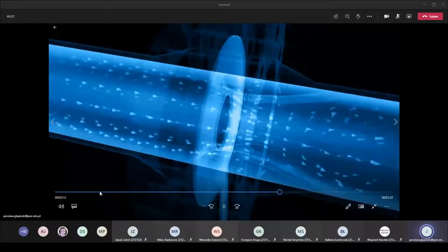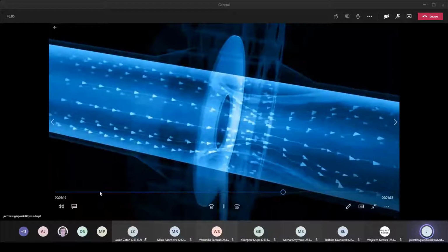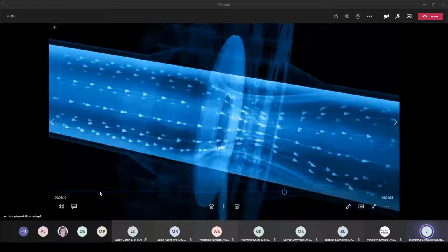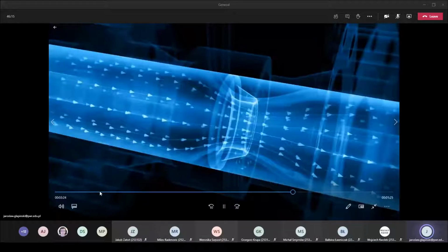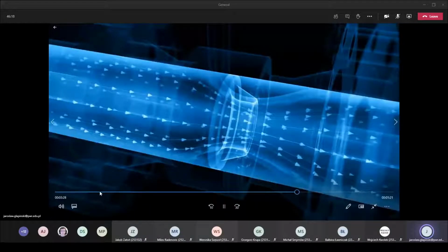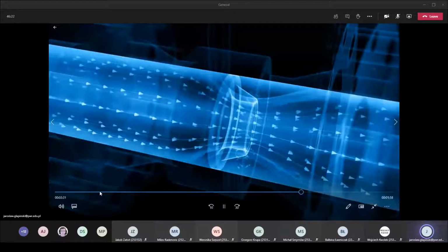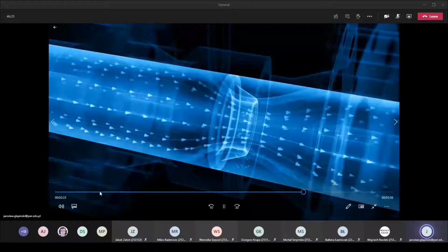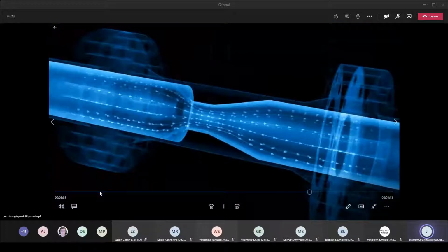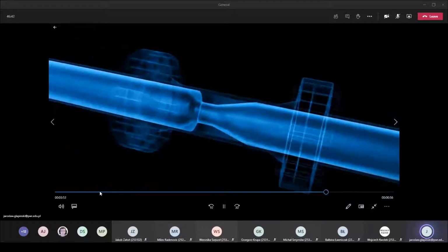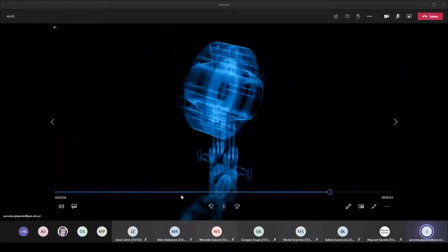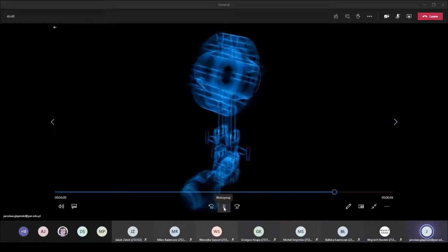This demonstration shows that an abrupt restriction generates severe turbulence in a fluid. Nozzles with a rounded, funnel-like inlet clearly reduce turbulence and thus create less pressure loss. Nozzles are particularly suitable for higher flow velocities or for fluids with abrasive solid particles. Turbulence reduction is even greater with Venturi nozzles. And finally, with Venturi tubes, where the restriction is created by longer conical constrictions in the pipe wall. All these designs can be supplied with different restriction diameter sizes, so that the pressure loss and the differential pressure generated can be optimized for the process conditions.